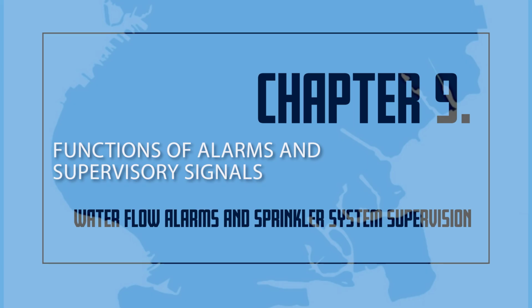Any signal, whether water flow or supervisory, may be used to sound an audible local sprinkler alarm. It may also send a signal to the central station company. The central station company will then contact the local firehouse. Supervisory devices are often connected to an approved central station company which monitors the sprinkler system for problems with equipment and when sprinkler heads are opened. The central station company should be notified when any control valves are closed for maintenance or repair. This reduces the number of false alarms.